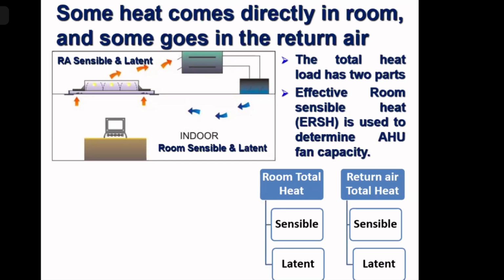What special importance? That heat we will take out by supplying cold air in the room. The cold air we supply in the room takes out only the sensible part of the room total heat. So we'll have to separately calculate room sensible heat to determine how much cold air we should supply in the room. And that will determine my air handling unit fan capacity. And that will determine my supply air ducting sizes. And that will determine my supply air grille or diffuser sizes and numbers. And that will also play a major role in sizing the chiller.